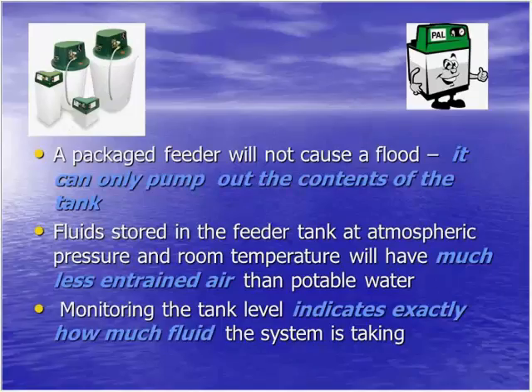And monitoring the tank level indicates exactly how much fluid the system is taking. If you've got a very minor leak, and you've lost a gallon over the course of the winter, you know that it's very small and it's something you should maybe get to and look at, but you don't necessarily have to shut the heating system down. If you've lost gallons overnight, you've got to find out where that leak is and repair it immediately.